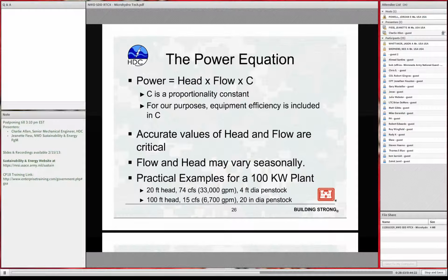And as you look at sites, be aware that flow and head will probably vary seasonally. As a practical example, just to give you a sense of what we're talking about here, at a 20-foot head site, which is roughly 8 pounds per square inch of pressure, you need 74 cubic feet per second or 33,000 gallons per minute being delivered through a 4-foot diameter pipe or penstock in order to generate 100 kilowatts. If you increase that head to 100 feet or approximately 43 pounds per square inch, then you only need 6,700 gallons per minute delivered in a 20-inch diameter penstock in order to generate that same 100 kilowatts.